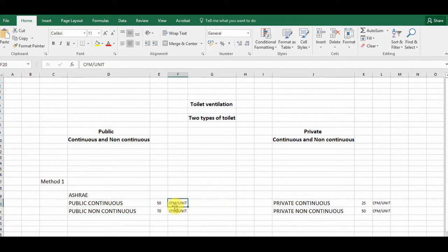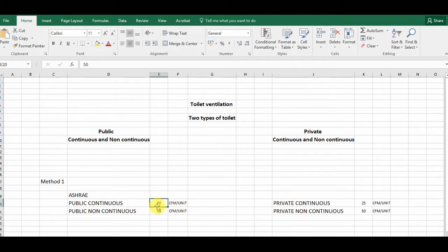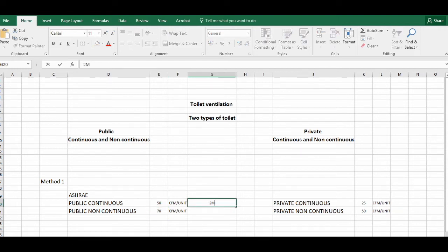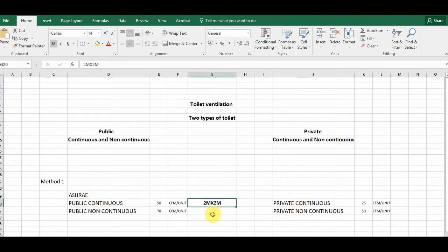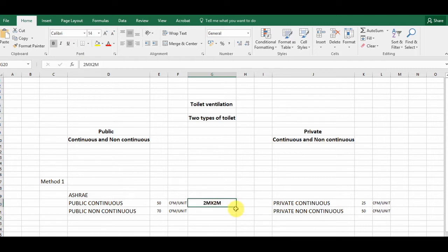In a public continuous toilet, we remove 50 CFM per unit. Per unit means per toilet — from one toilet we remove 50 CFM. CFM is cubic feet per minute, so in one minute we remove 50 cubic feet of air from the toilet. The standard toilet size used here is 2 meters by 2 meters.